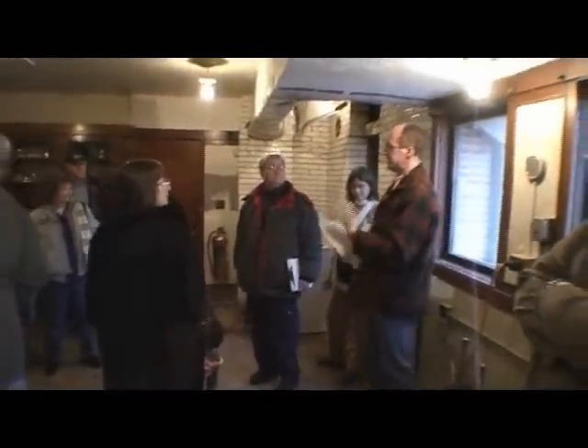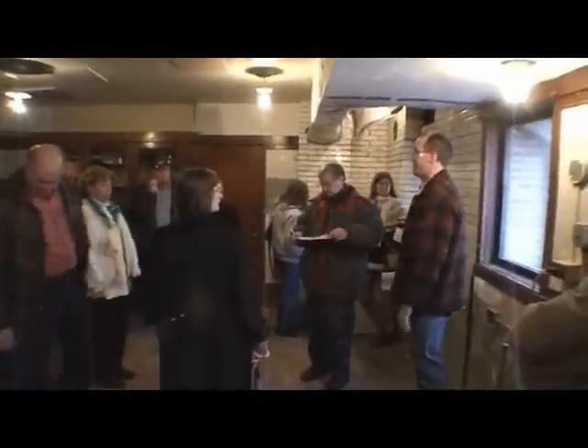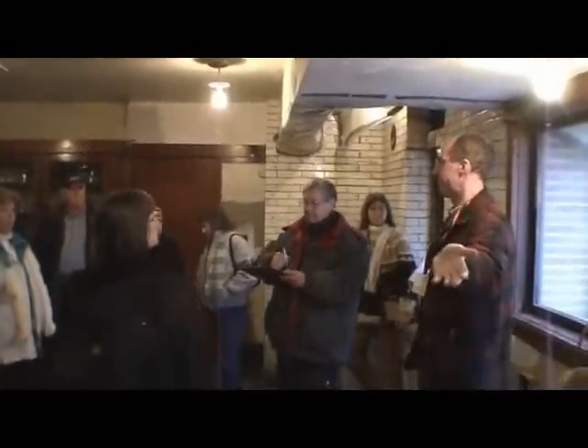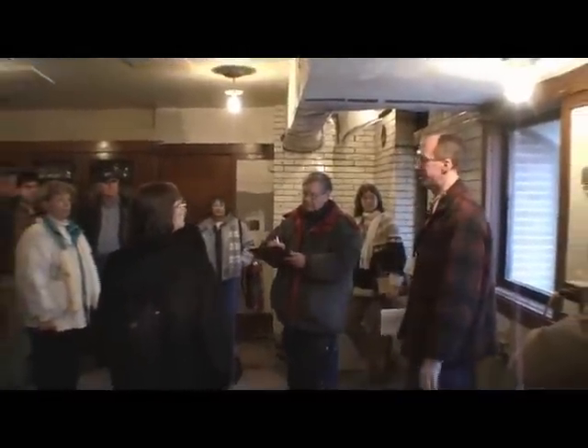All right, I think I've touched on that stuff. I'll tell you about our sprinkler system. We have a combination system in this building. There's sprinklers throughout, as you've seen, but they're in what's called a dry pipe system, so there's no water in the pipes right now. There's only water in them if one of the sprinkler heads opens up. That's because when water's in these pipes, condensation can form on them that drips down onto the building surfaces, and that can damage plaster and things like that.